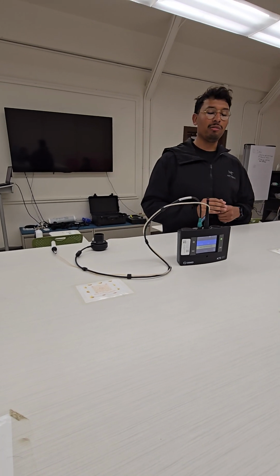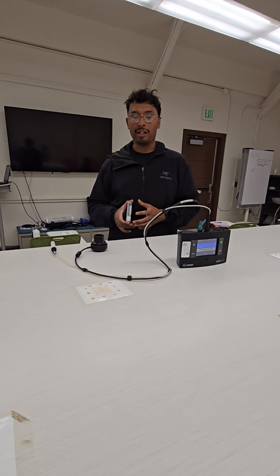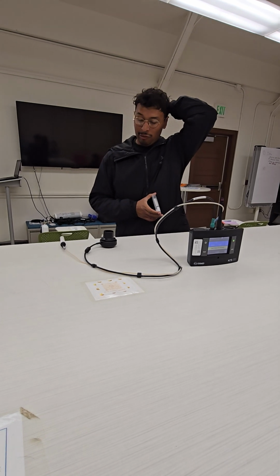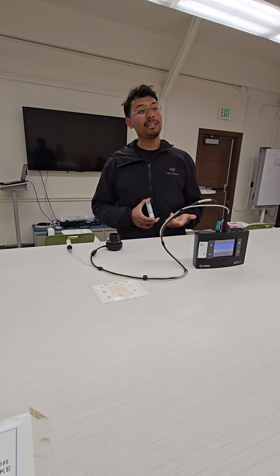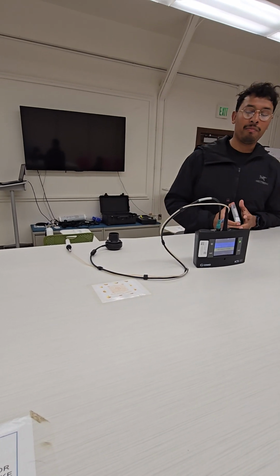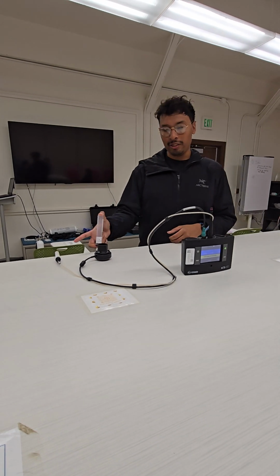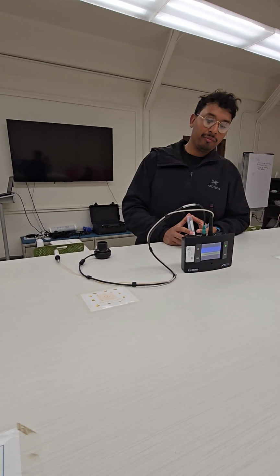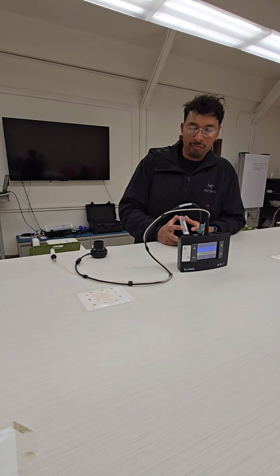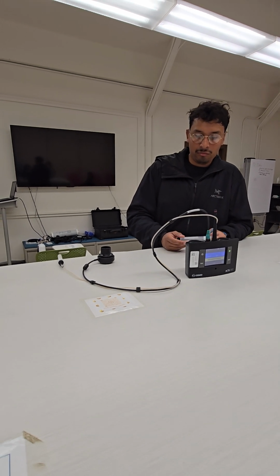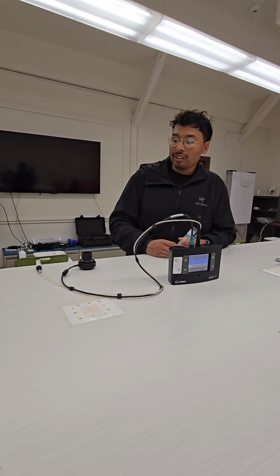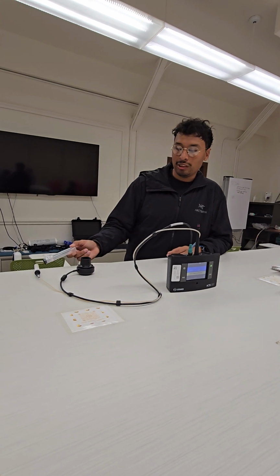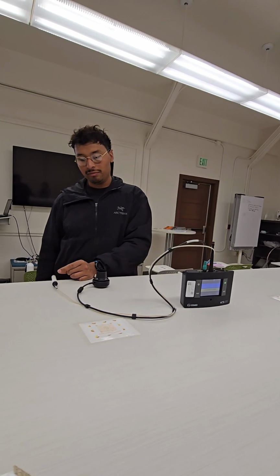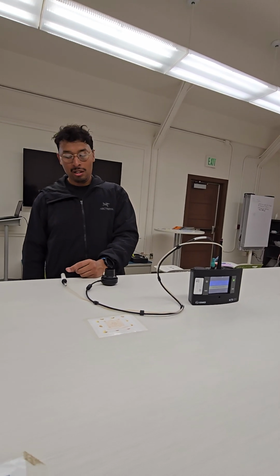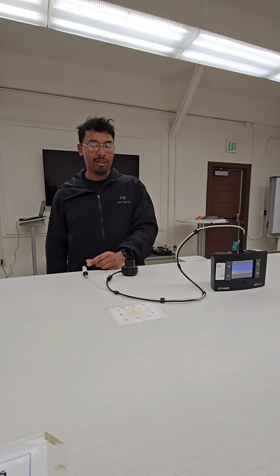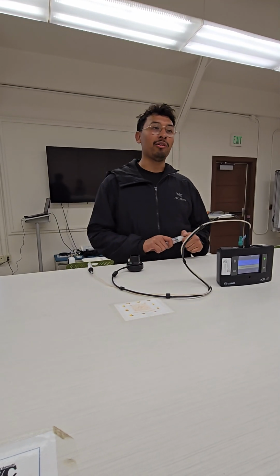If you do fail the CO2 scrubber calibration, the first thing we recommend is to try a different sampling line. If it keeps failing, then it could be the tube itself. But over time, the rocks will start to turn purple towards the end. It's a really light purple. Once it's a quarter of the tube purple, then it might be time to replace it.